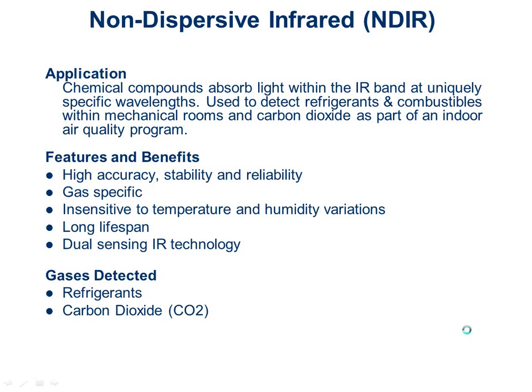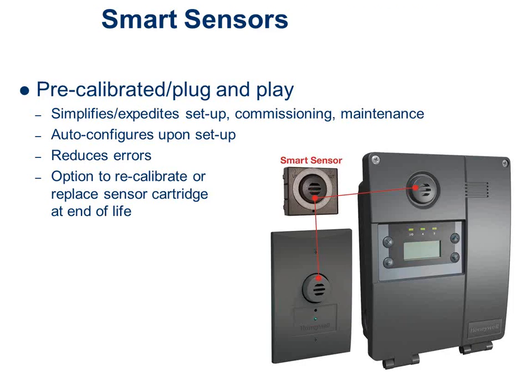A lot of these sensors, depending on what gas you're detecting, come in different flavors. Sometimes you have a dumb sensor that just reads the value and spits out a signal to somebody else's controller or building automation system, which has to do all the work. Other times the sensor has a controller built in, like the one shown on the right, which reads the sensor, compares it to the set point, and has relays or speed controllers for fans to turn things on and off.